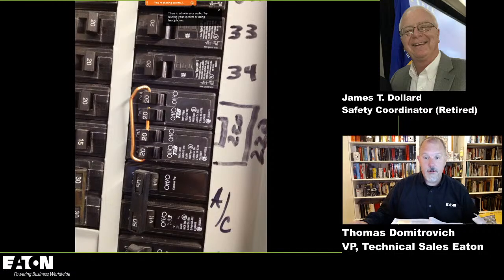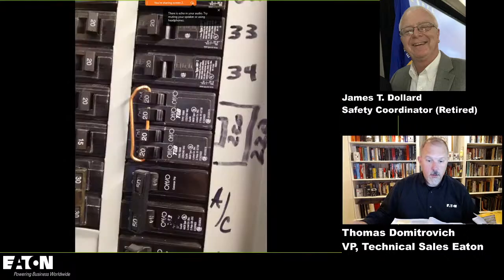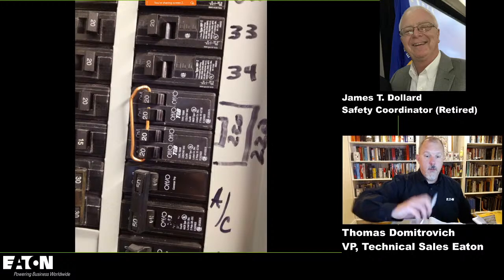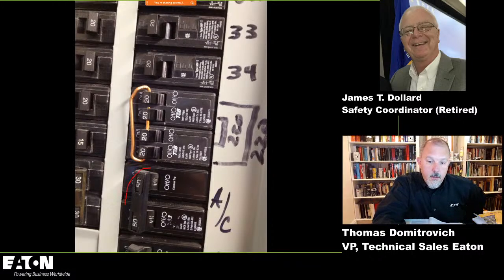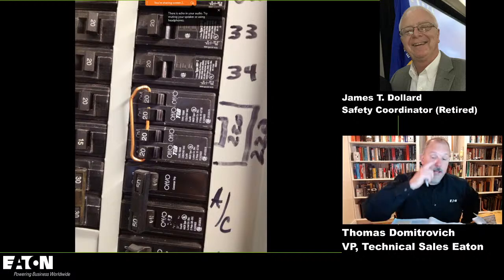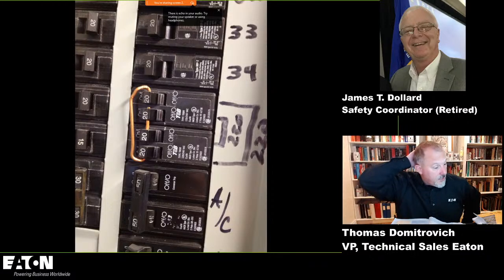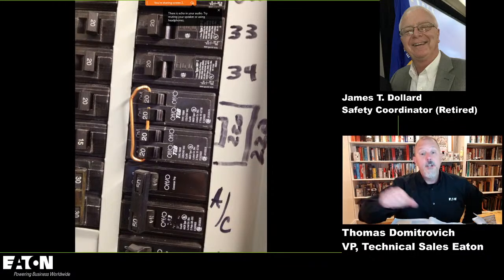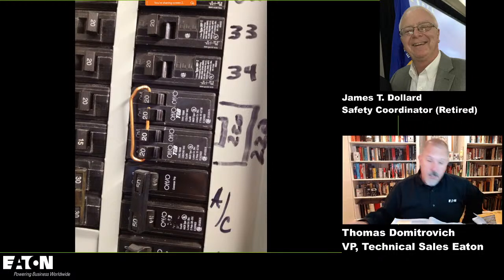Absolutely right. And the one below it is a common trip, not a handle tie, because you see the text only on one side. So that's a common trip. And it even says on that top one, common trip, you can see it. Yeah, that's right, it says common trip right there. And the requirement for a multi-wire branch circuit isn't common trip. That's right. It's simultaneous disconnect. Yeah, absolutely. And the whole purpose there is that when you do disconnect it, you take off both hots and disconnect and isolate that circuit.